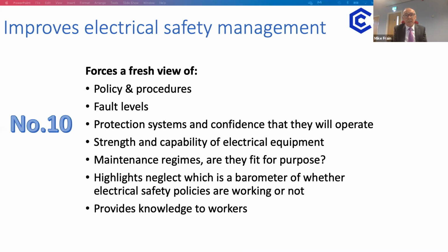I repeat that. The worst excesses I've seen over the years, and I've got a gallery of horrors from going around various factories and commercial networks, I can tell you that you look at electrical safety panels, and one thing that wrecks them is either water or ingress of something else, or electrical workers in many cases. You find that particularly safety equipment like actuating bars, insulation, trunking lids, and ingress of God knows what in there is a direct result of the people actually maintaining the equipment itself. Sorry to go off on a rant, but if you take a proper look at an audit of the electrical system, these things will come up.